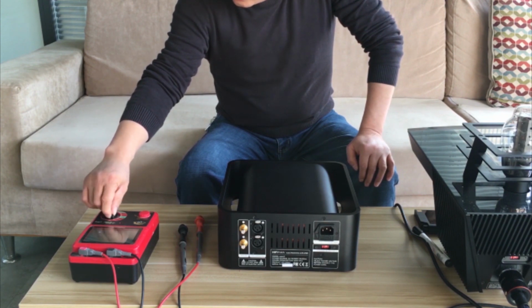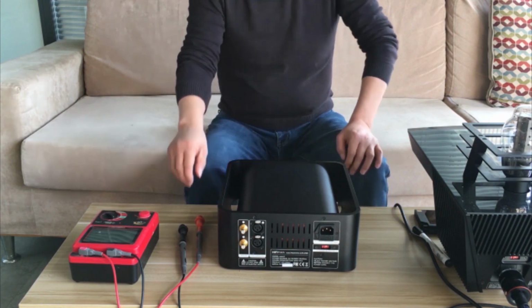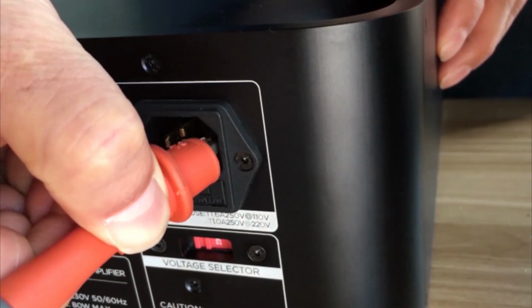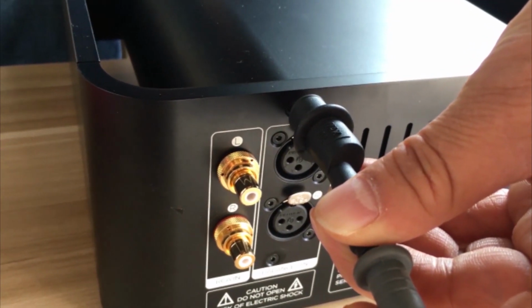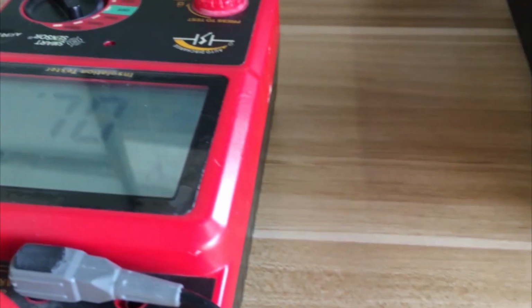We will start by setting the test voltage at 1000 volts DC. We will connect the neutral and live wires of the electrical socket to test the electrical insulation between the transformer and the ground.